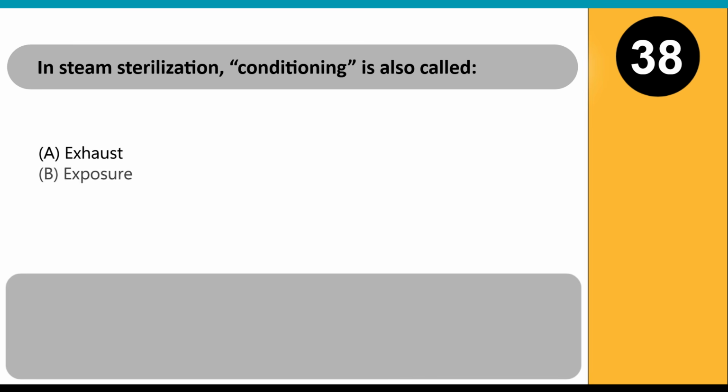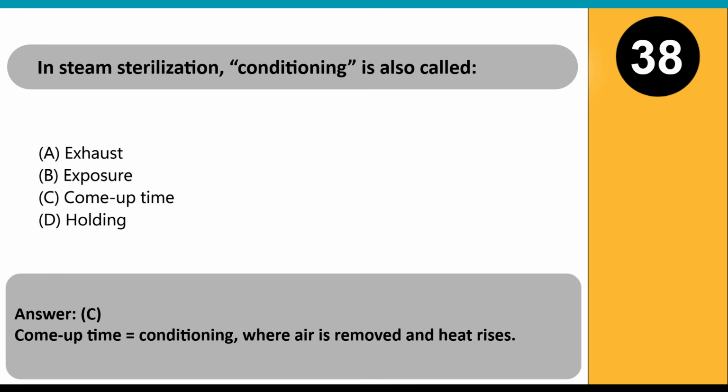In steam sterilization, conditioning is also called A. Exhaust. B. Exposure. C. Come-up time. D. Holding. Answer: C. Come-up time equals conditioning, where air is removed and heat rises.